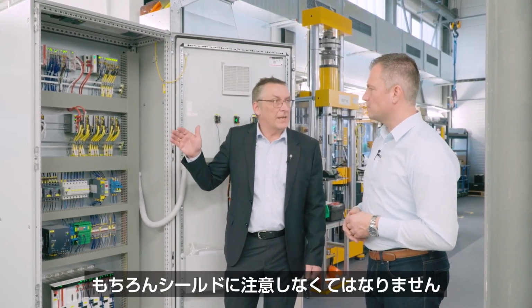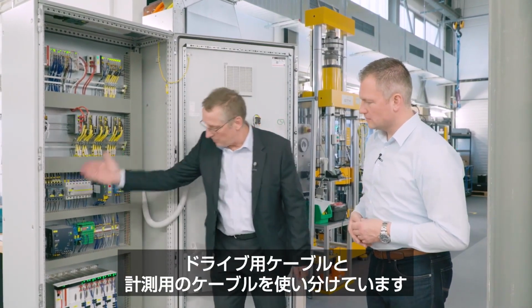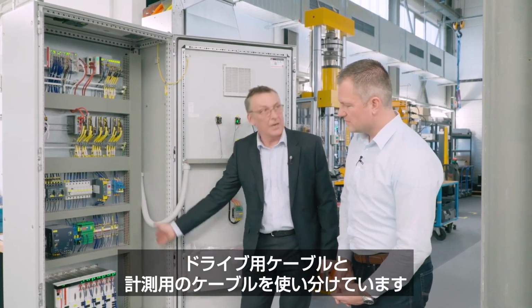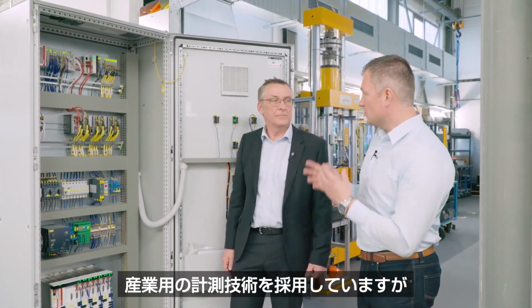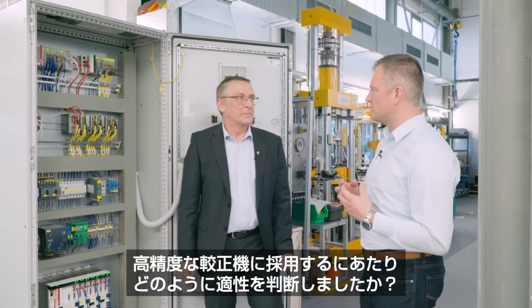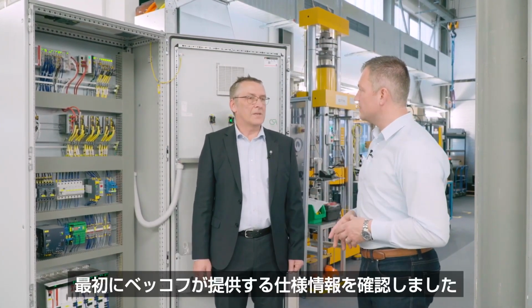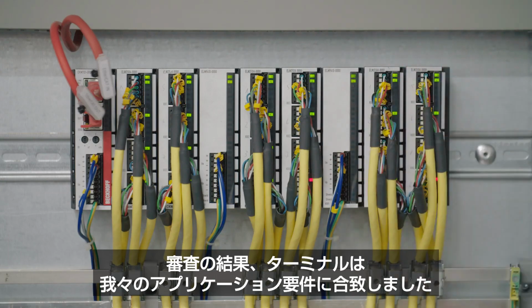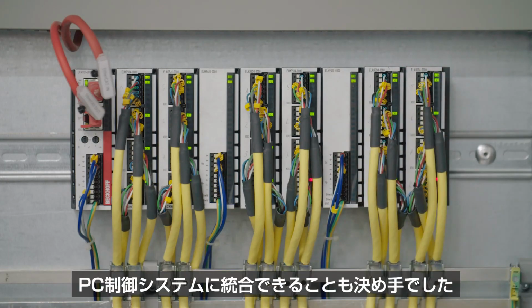Yes, of course, you have to take care about the shielding concept. So we have different cable routes for the drive system and for the measurement cables. Okay. And you use industrial-grade measurement technology. How did you qualify it to be used in such a precise calibration machine? Yes, at the beginning we had to look into the data sheet of Beckhoff, and we looked for the properties which are interesting for us. But we are also an accredited laboratory for voltage ratio. So we had the possibility to do a very critical investigation of the terminals, with the result that the terminals are well suited for our application, and the advantage is that they are integrated in the whole PC-operated system.